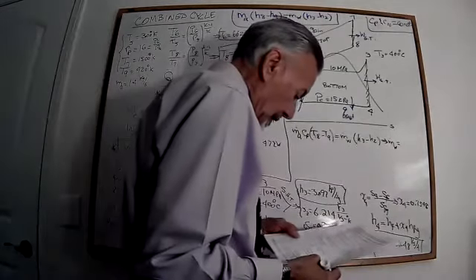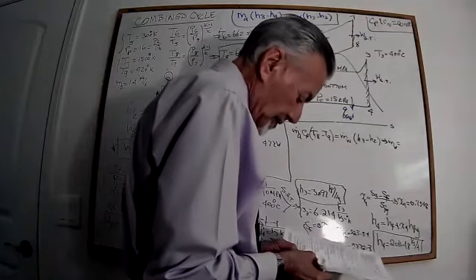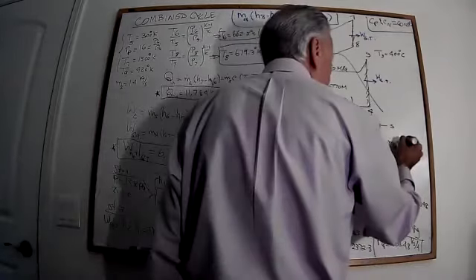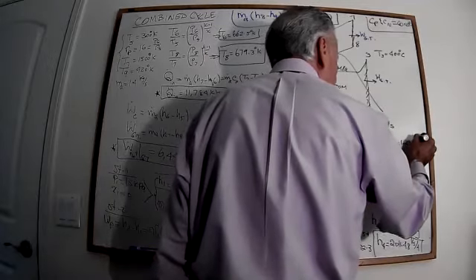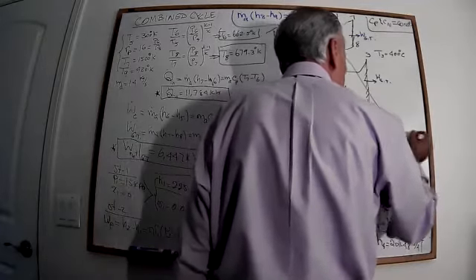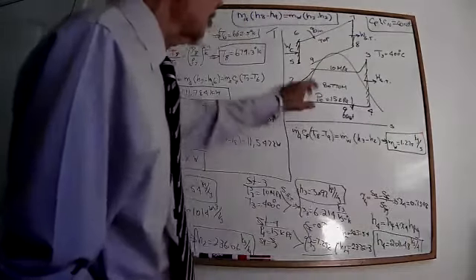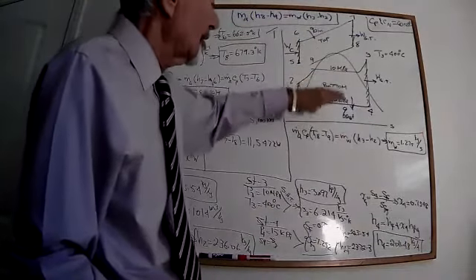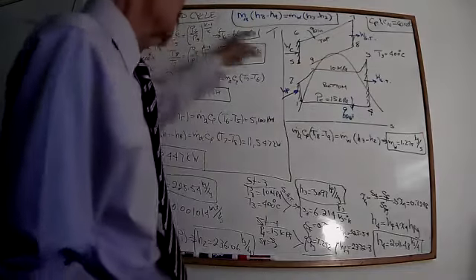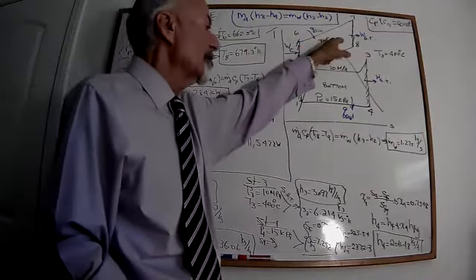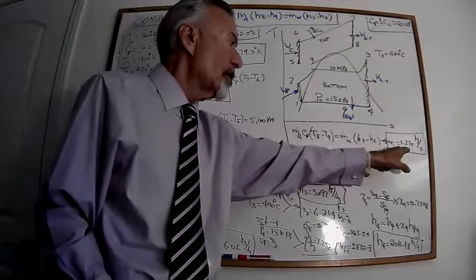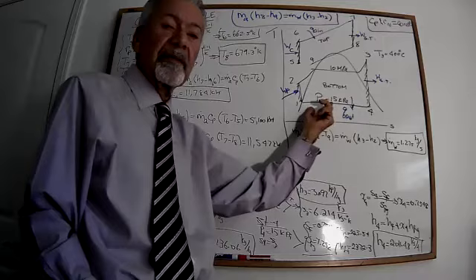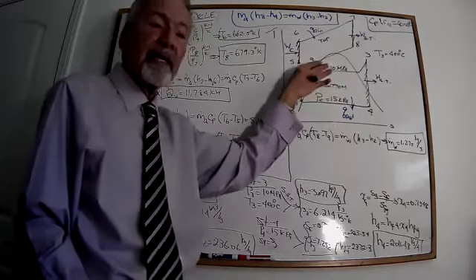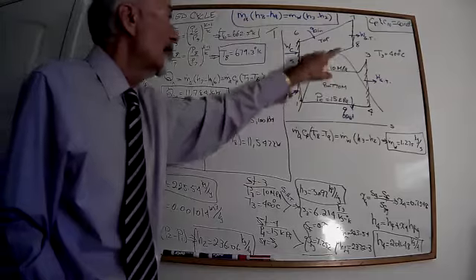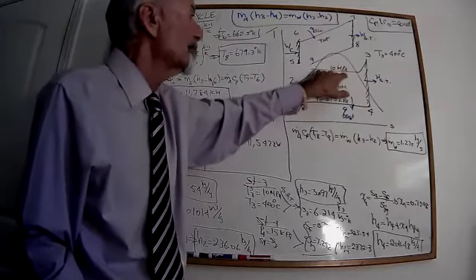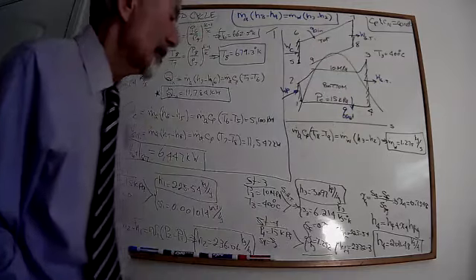In this case, the mass of water becomes 1.275 kilogram per second. This shows me, in order for this system to work under the conditions we have, for every 14 kilogram of air that goes through the top cycle, I need only 1.2 kilogram of water going through the bottom cycle in order to balance it out. That's why we write this relationship between this part, the boiler, and the Q out of the other cycle.